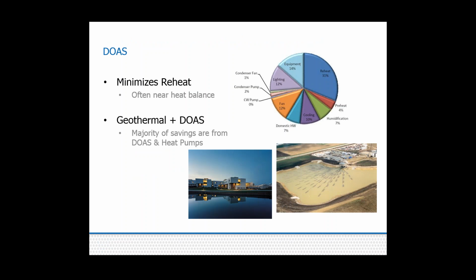Another option, at least if you're doing a new building, is dedicated outside air. The biggest savings there is avoiding reheat. I included the pie graph there for a typical VAV reheat hospital. It's even worse if it's a constant volume facility, where reheat is typically the biggest piece of the pie. And the picture I've got in the lower left there is a Great River Medical Center in Burlington, Iowa. And one of the things with the DOAS, that's actually a geothermal heat pump with DOAS.